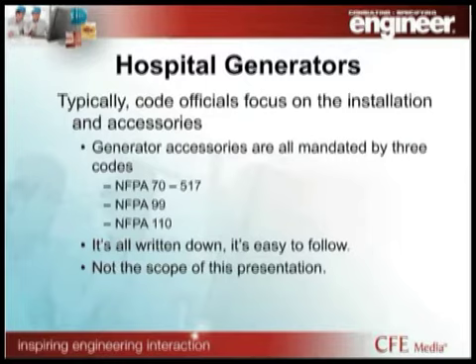So first off, generators typically are very codified for a hospital environment. All the accessories, where we put them, the environment that we install them in, and how we maintain them is written down. As Dwayne would say, it's prescriptive. It's like following a recipe. We see a lot of this language in NFPA 70, 517. We're also informed by NFPA 99 and 110. And as the slide says, it's all written down. It's easy to follow, and it's really not the scope of what we're going to cover today.